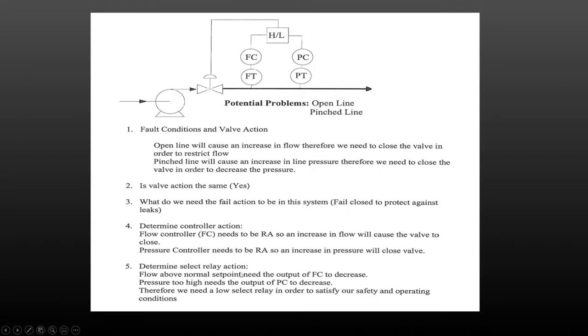Then we determine the relay action. Flow above the normal set point requires the flow controller output to decrease. If pressure is too high, we need the pressure controller output to decrease as well. Therefore, we need a low selector relay to satisfy our safety and operating conditions. That's the process — 90% of the applications we look at are going to be low select, with the exception of the reactor temperature example.